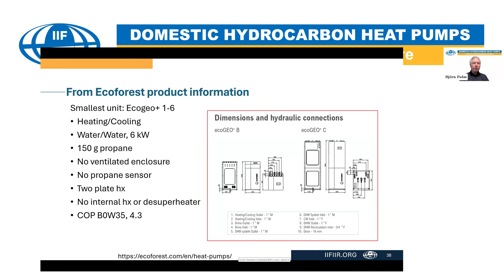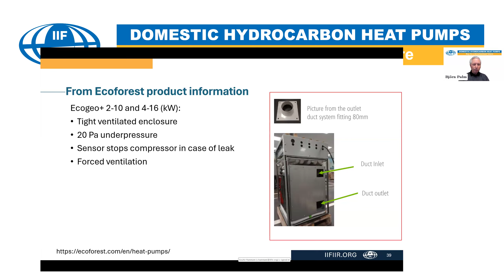The same company also has units with larger capacity, up to 16 kilowatts. In this case, the units have a tight ventilated enclosure, designed so that you constantly have a slight under-pressure inside this tight enclosure. The enclosure is connected to the ambient by two ducts, and you have a fan which can evacuate the enclosure rapidly in case of a leakage. So there is a sensor which stops the compressor in case of a leak, and also starts the fan with forced ventilation. That is how the larger charge is handled according to the standard which Daniel told you about before, 60335-2-40.